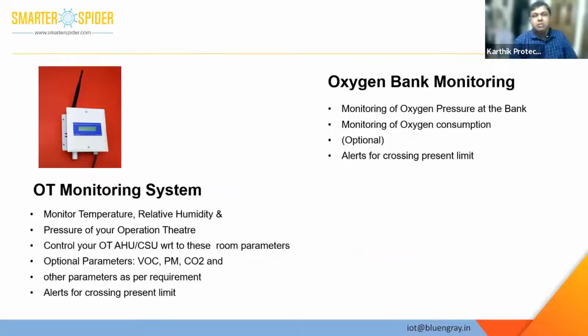Coming to other applications which we have is the OT monitoring system, where it monitors the temperature, relative humidity, and pressure of your operation theatre. It controls your OT, AHU, or CSSD with respect to these parameters. We can even provide optional parameters such as VOC, PM2.5, CO2, and other parameters as per the requirement, and we have alerts for crossing the preset limit.